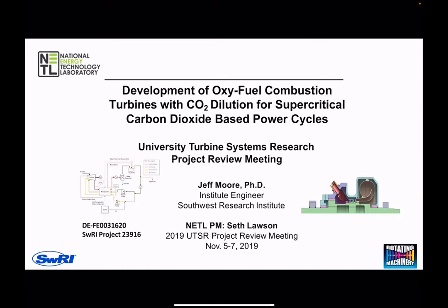Absolutely, thanks Tim. I'm going to go over a couple of the projects we've been leading on the development of these oxy-fuel turbines. Both are in the 300 megawatt range. One is a natural gas-fired cycle, similar to the cycle currently in development. Then there's also a coal syngas combustion cycle, similar to the natural gas one, except we're using a gasifier coal syngas cleanup process, which takes a pretty good hit on cycle efficiency. That one was funded under the Coal First program.